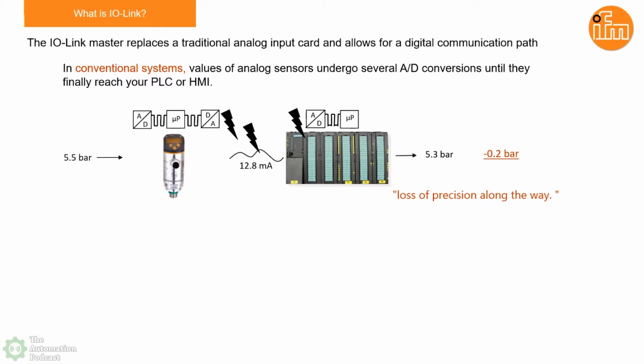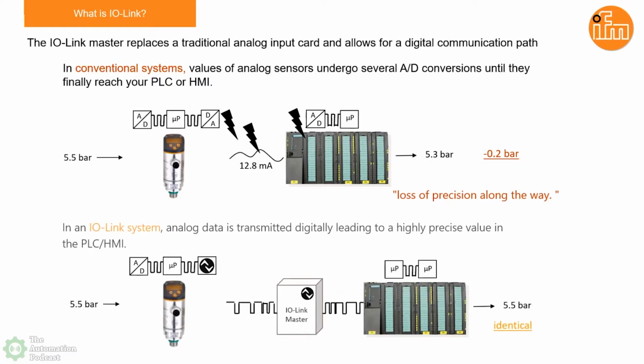Now when we take the same situation but use IO-Link instead, you can see we only do one A/D conversion - from the sensing element side of the sensor. From there, everything else is transferred digitally to the microprocessor. So we're eliminating at least 2 A/D conversions within the cycle, and because of that, we're able to give a much more accurate signal at the end of the transmission.